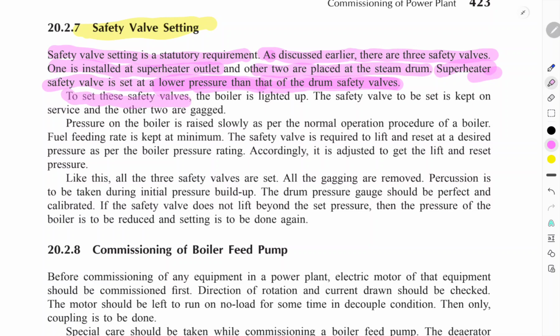To set these safety valves, the boiler is lit up. The safety valve to be set is kept in service and the other two are gagged. Pressure on the boiler is raised slowly as per the normal operating procedure of a boiler, with the fuel feeding rate kept minimum. The safety valve is required to lift at the desired pressure as per the boiler pressure rating. Accordingly, it is adjusted to get the lift and reset pressure. Likewise, all three valves are set.